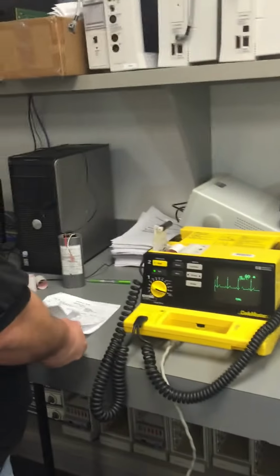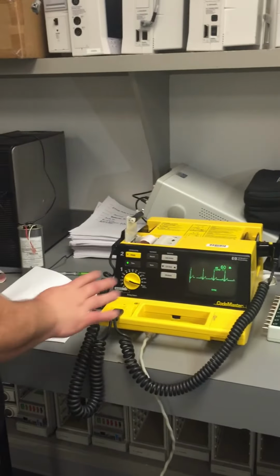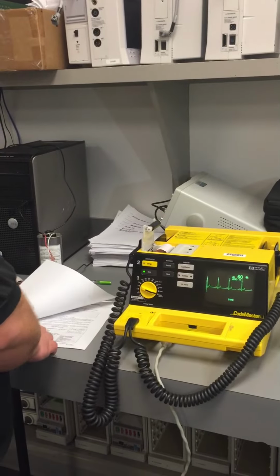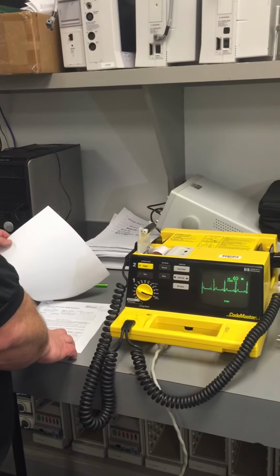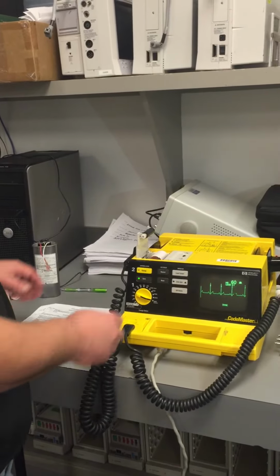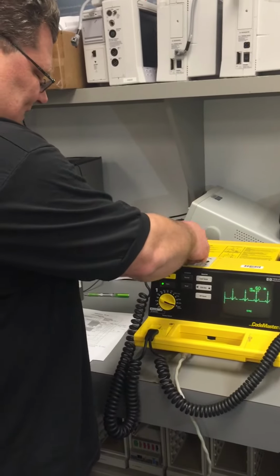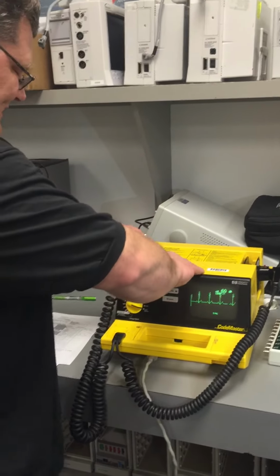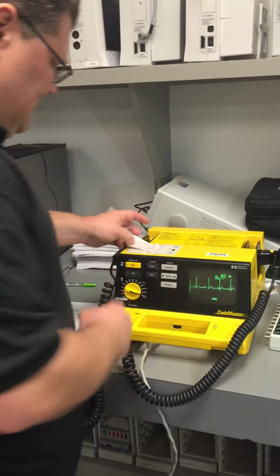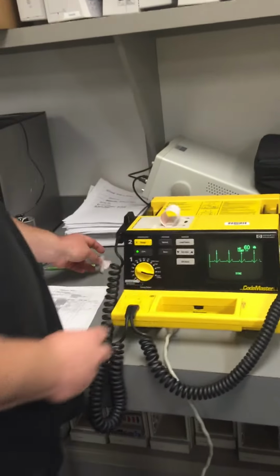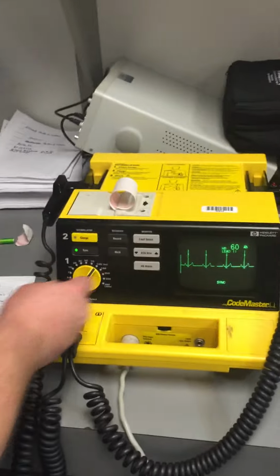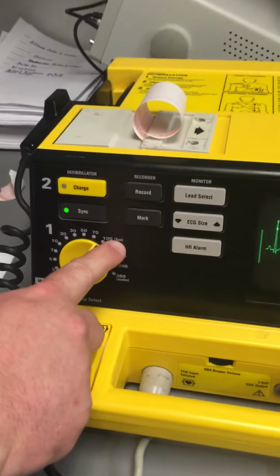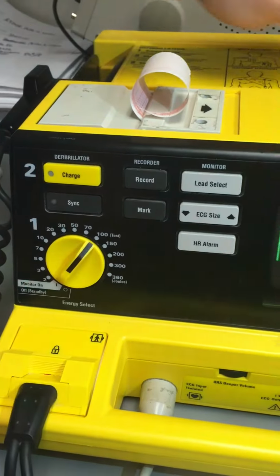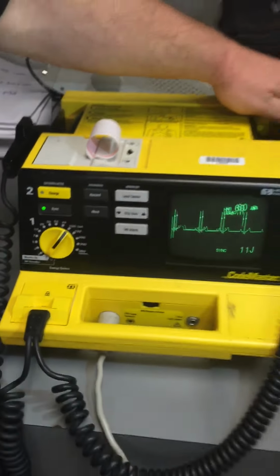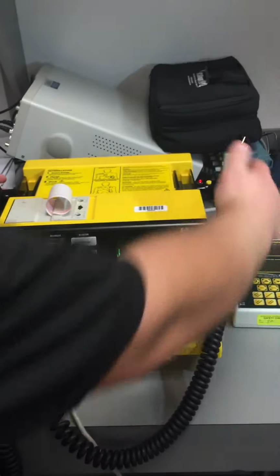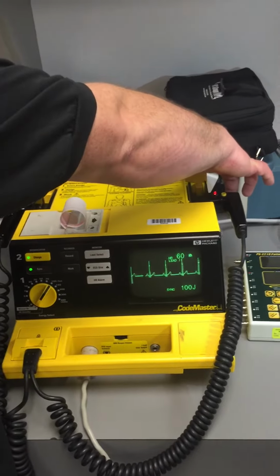Let me see what else we've got to do that is specifically a defib only check. Looking at this, I'd say the next big thing is the self-test. After we're all done here, and I like to do this with the 60 beats per minute on there because this is going to print something for us. Charge the defib to 100. You see that it says test here. This is the self-test for the device. I'm going to charge, and I'm going to discharge in the wells here.